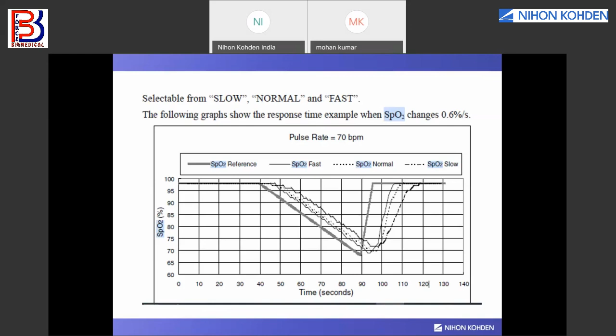But when there is some artifact like patient hand movement, excessive movement, as you see in neuro ICU or NICU, neonatal ICU, there is an excessive movement of limbs. In that case, you can choose the slow SpO2 response time. This will synchronize the movement with the SpO2 filtration. This we can achieve through adaptive filter, as we saw in the previous session about what is an adaptive filter. Adaptive filter minimizes the artifact due to movement of the patient, due to patient conditions like neuro ICU or NICU.